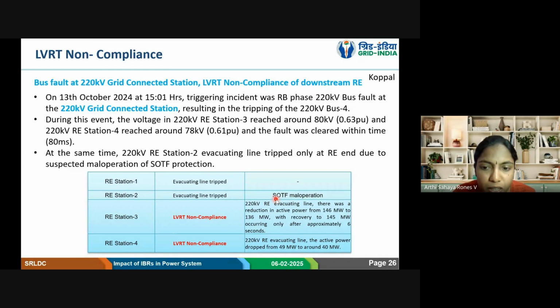During this particular event, this line, which was already in close condition, got tripped due to the SOTF maloperation. This issue was later rectified because the SOTF enable function was manually set high. Due to that, when a fault happened nearby, when the current pickup had reached and the SOTF initiation was high, this RE evacuating line had tripped. Later in that relay, the manual high SOTF function was changed, so it was made auto.